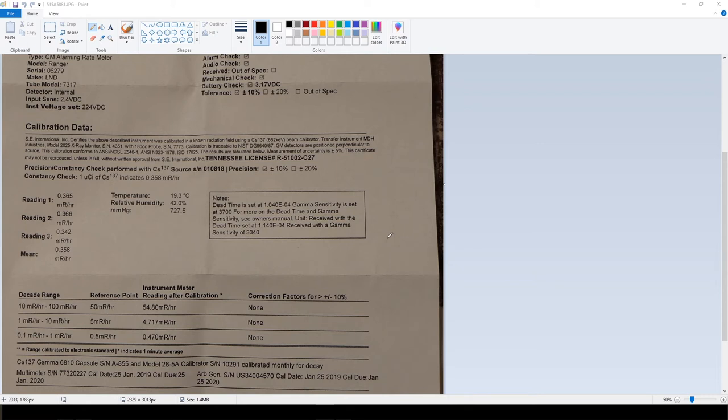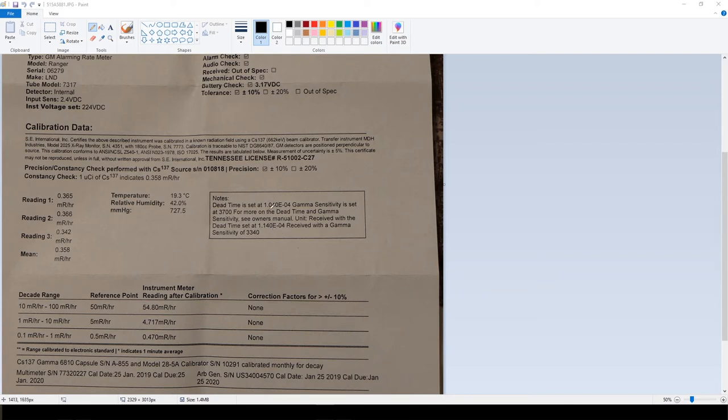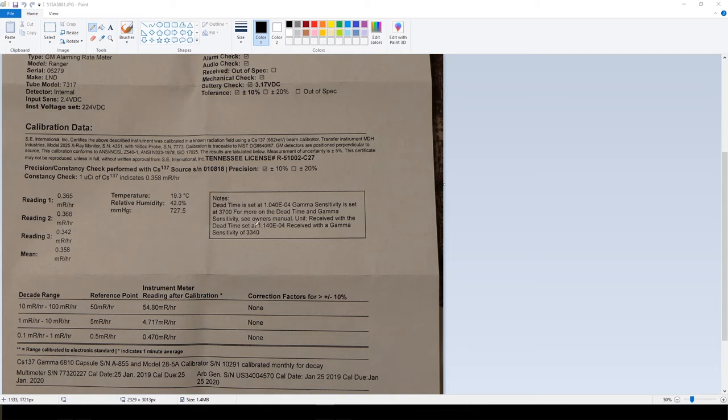They changed the dead time to 1.04e-04, and it was 1.140e-4, so slightly smaller number for the dead time. And they also increased my gamma sensitivity to 3700 when it was at 3340. I'll show you guys on the software that's provided with the Geiger counter what they actually did in the cal panel.